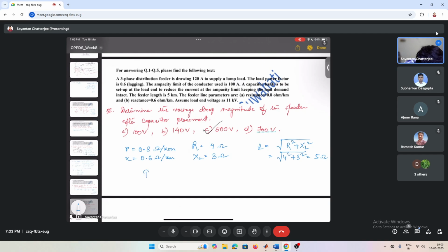After capacitor placement, the current would be limited to 100 ampere itself, because our aim is to not exceed the ampacity limit of the conductor. So the current will be the load current, we can say line current, 100 ampere after capacitor placement. So the total voltage drop would be I Z, considering this to be the magnitude. So this is 500. Any doubt? This is the answer. I think it's clear for everyone, right?